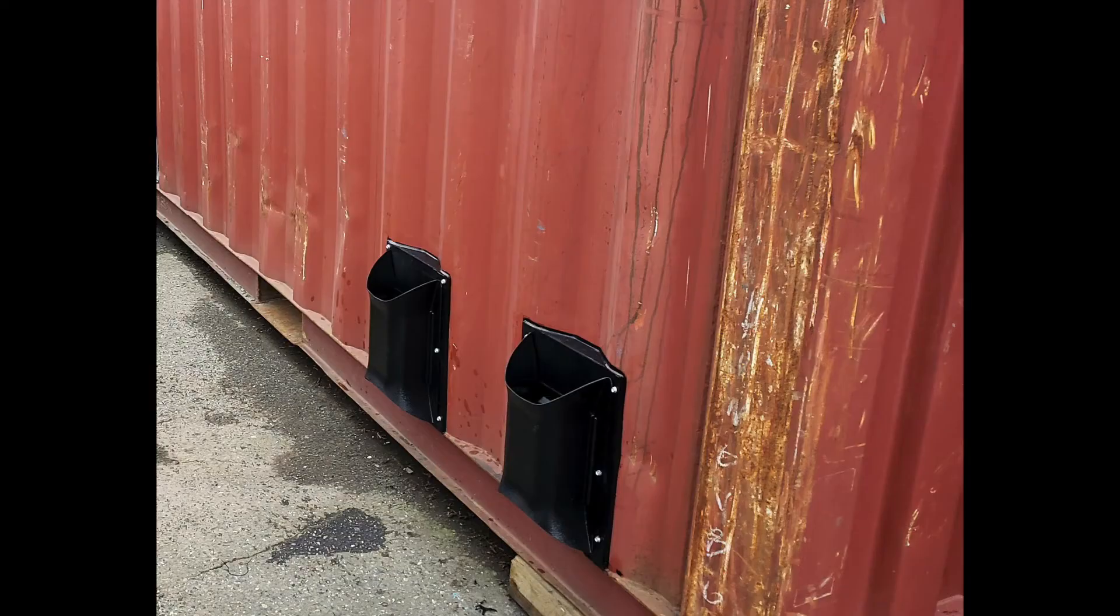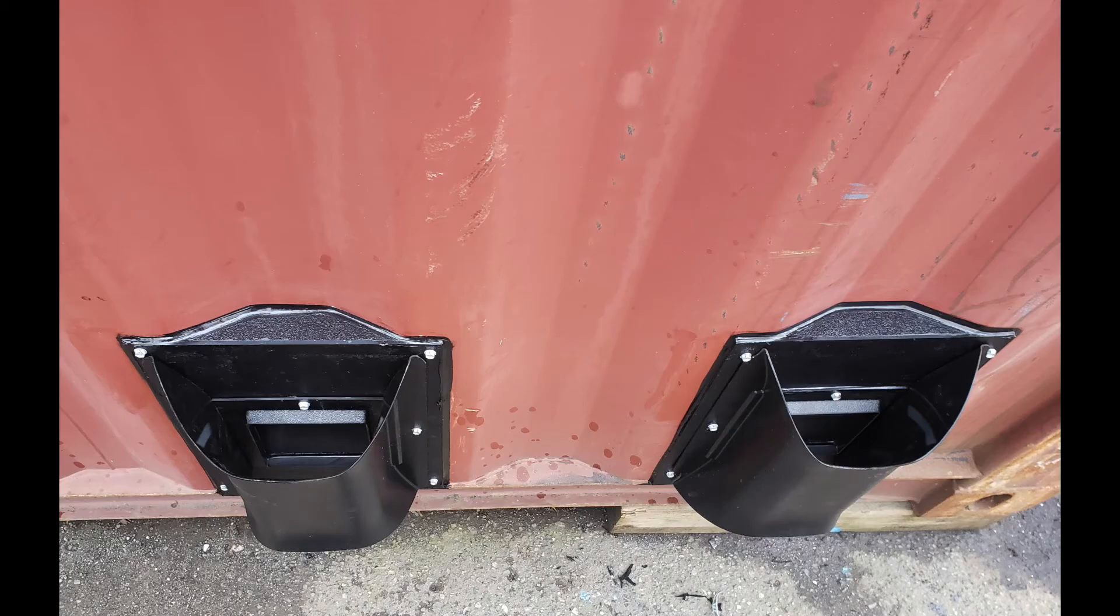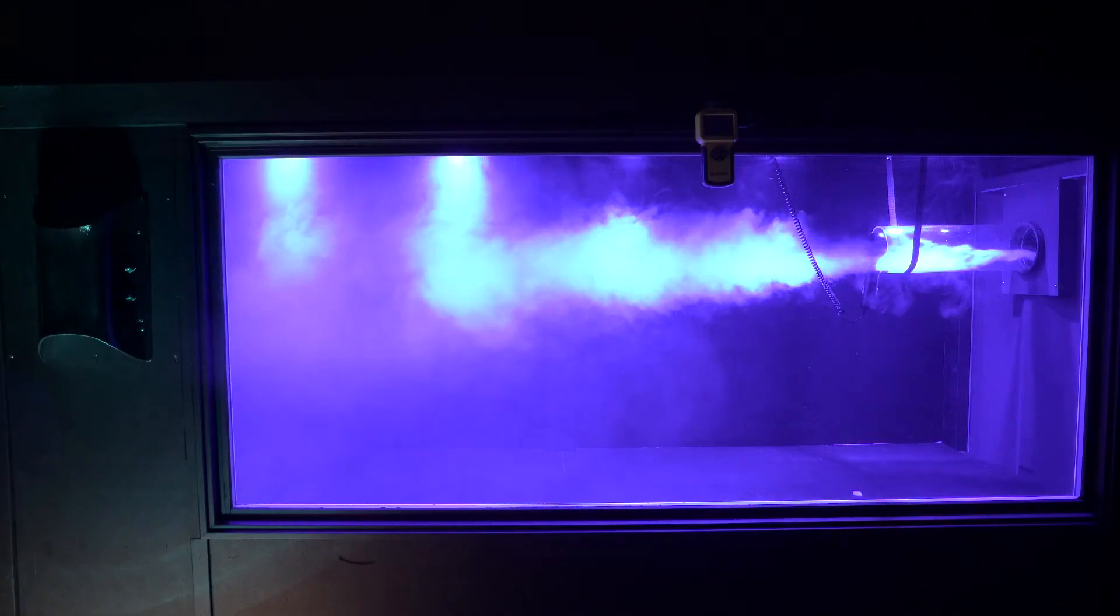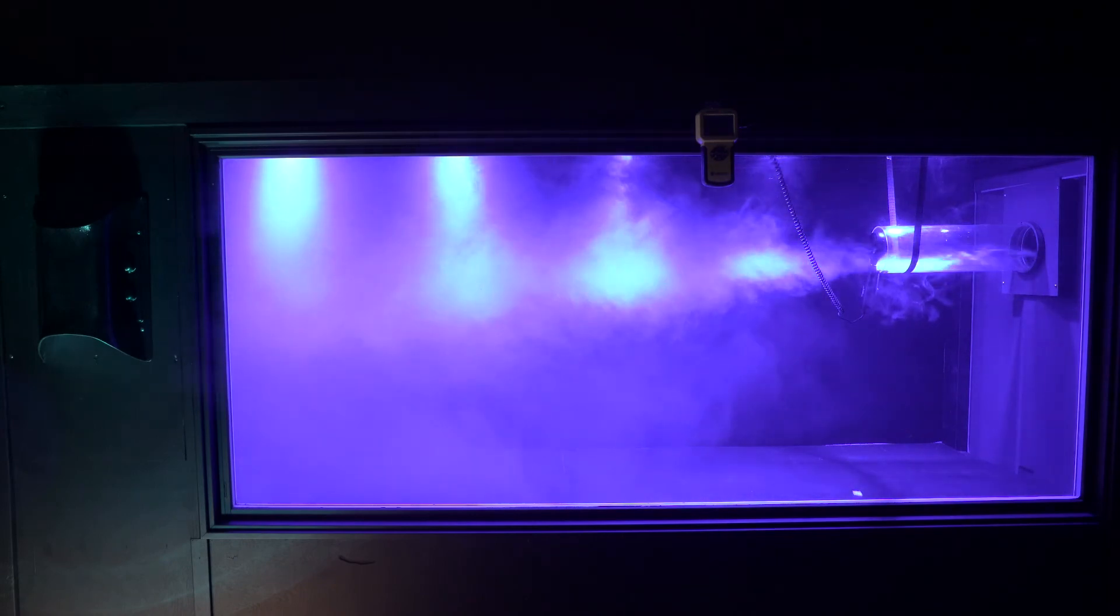This mounted exhaust driver allows for an easy, waterproof installation. But more importantly, it can be located wherever it is required. Floor level for fumes and gas extraction, or ceiling height for heat and moisture control. For a 40-foot container, two of our exhaust drivers are recommended and will move more air than a 12-inch turbine, even with half of the opening size.